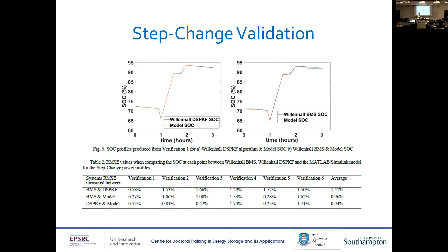This illustrates why the BMS is considered less accurate than the DSPKF algorithm. You can see these little steps because the granularity of the BMS system isn't as strong as the DSPKF - it only goes in increments of 0.1. So where you might have 90.19846, you'll just see 90.2. It's a little harder to get accurate with the BMS compared to the very high resolution that both our model and the DSPKF algorithm have.